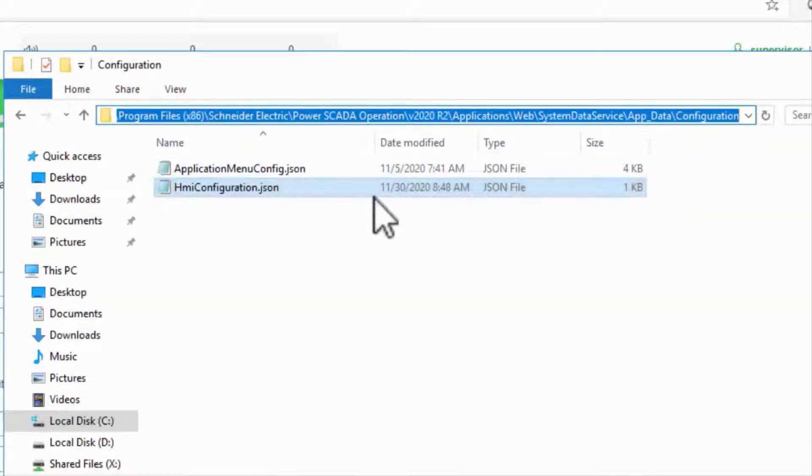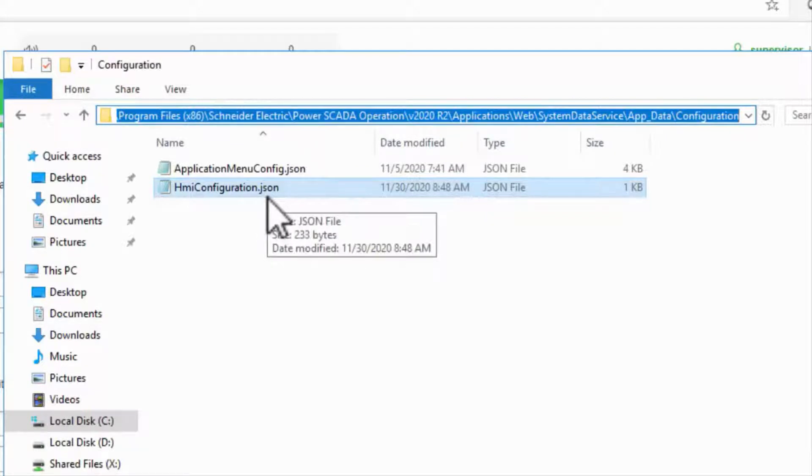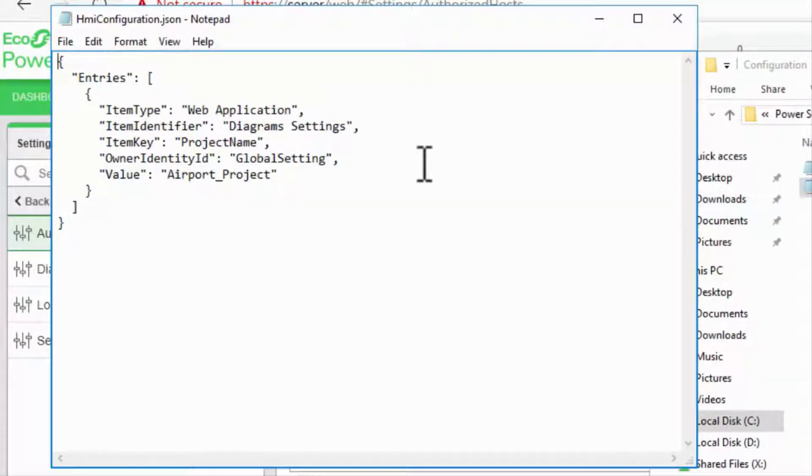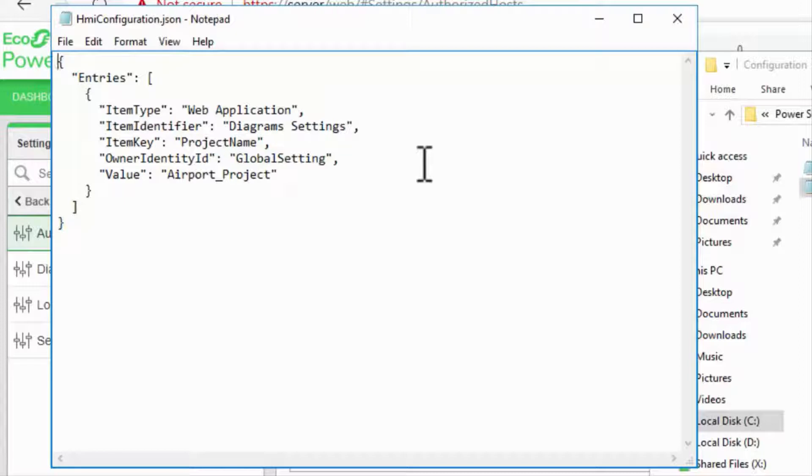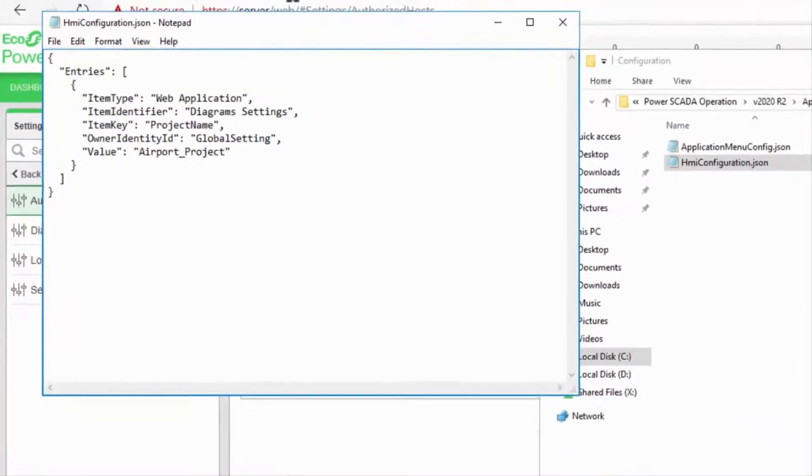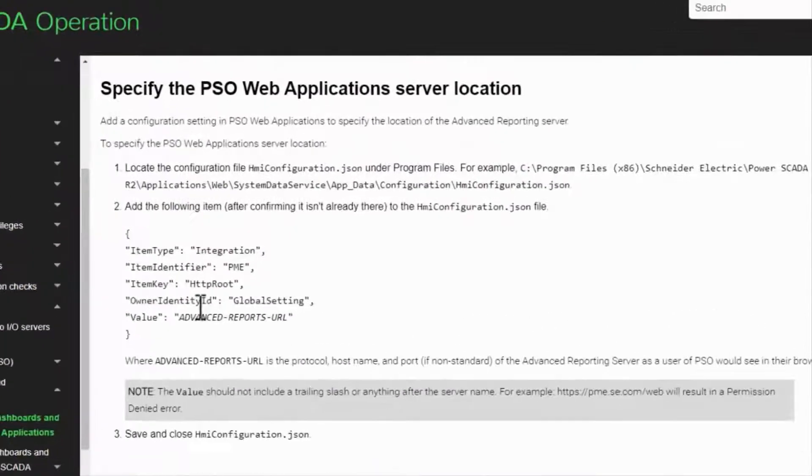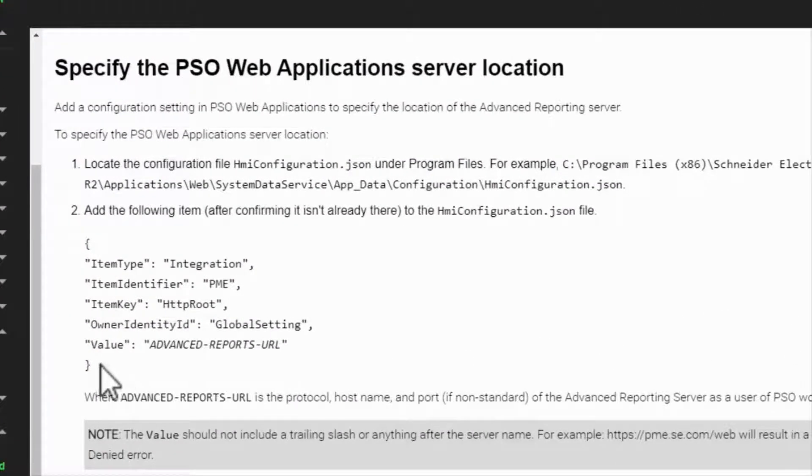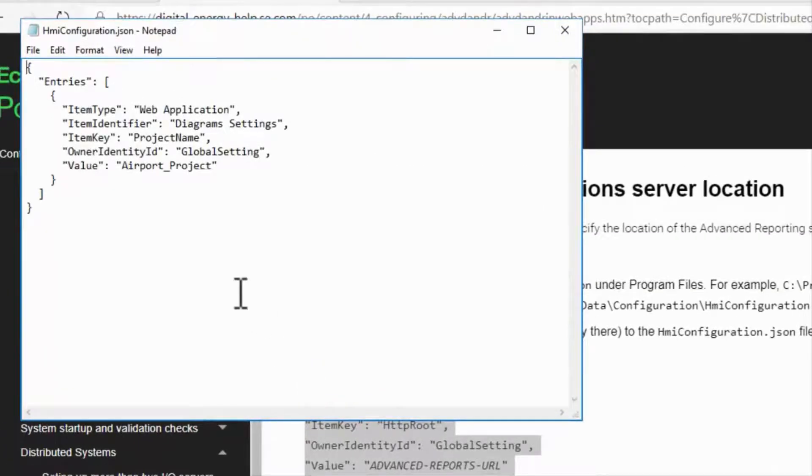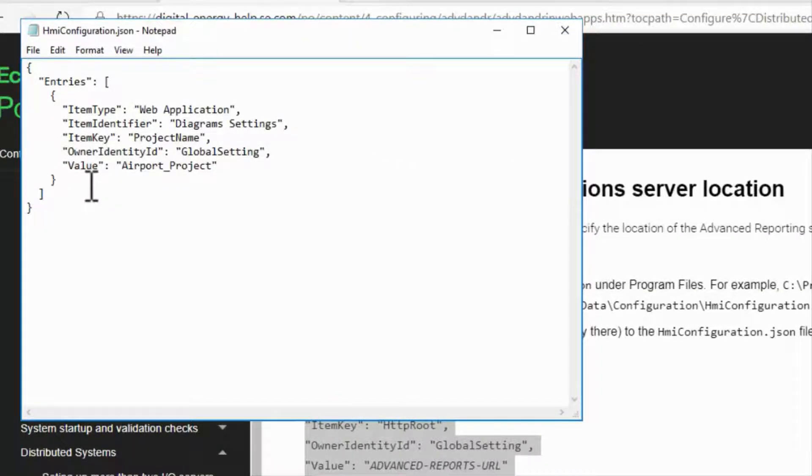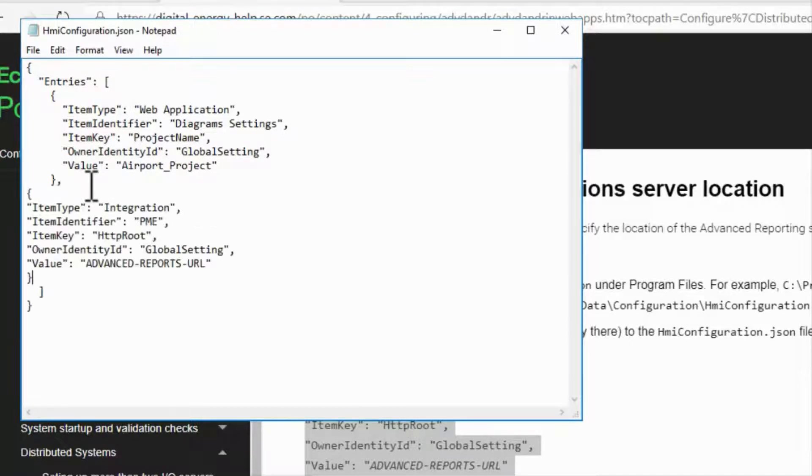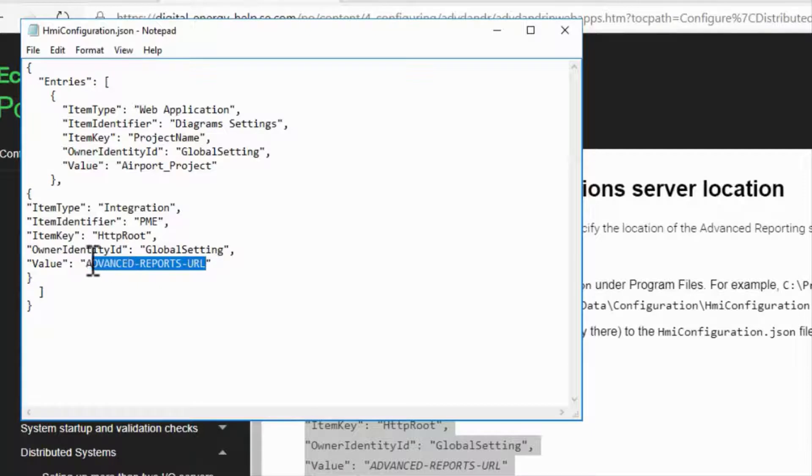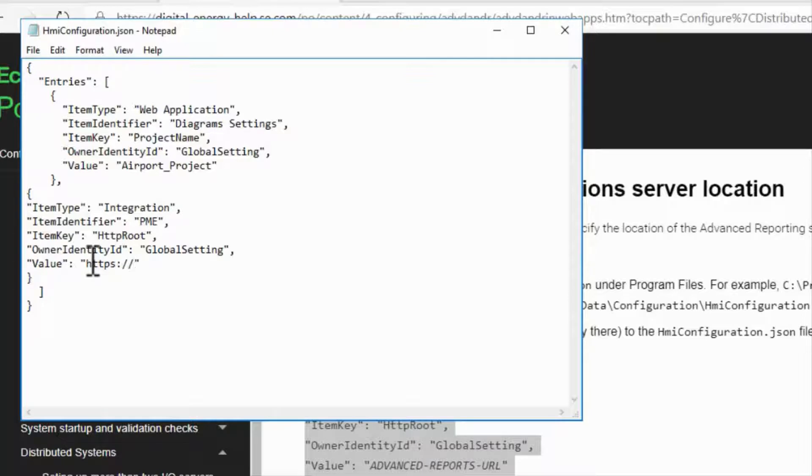The first file is HMIConfiguration.json. This tells the server where Advanced Reports lives and needs to be configured whether AR is on the same server or not. If this file doesn't exist, you need to run the WebHMI once to create it automatically. Copy the first JSON object from the System Guide and paste it inside the Entries list, making sure to add a comma after the first entry. We only need to change Advanced Reports URL to the full server name. In this case, https colon slash slash server. Save and close this file.